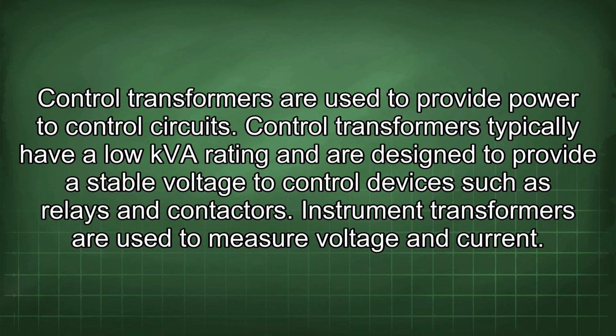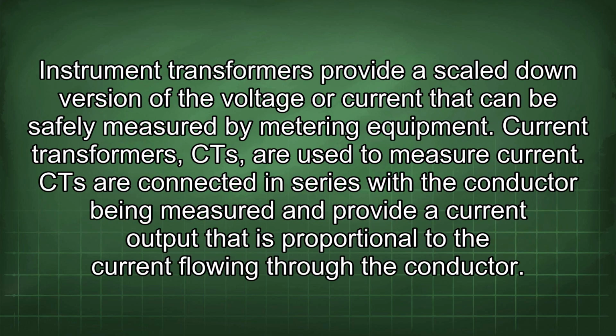Control transformers are used to provide power to control circuits. Control transformers typically have a low kVA rating and are designed to provide a stable voltage to control devices such as relays and contactors. Instrument transformers are used to measure voltage and current. Instrument transformers provide a scaled-down version of the voltage or current that can be safely measured by metering equipment.